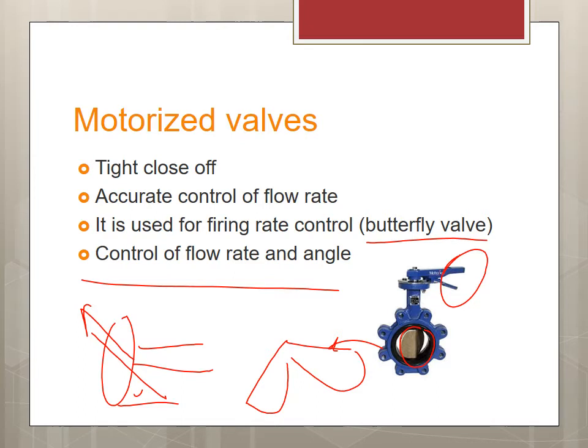An additional feature of motorized valves relates to locked rotor amperage and full operating amperage. When the motor closes completely, the amperage increases, and we can read that amperage to know whether the valve is completely open or completely closed. We can also control half-open by timing — there's a timer that tracks how many turns it takes to turn that valve to half, quarter, or one-third open.